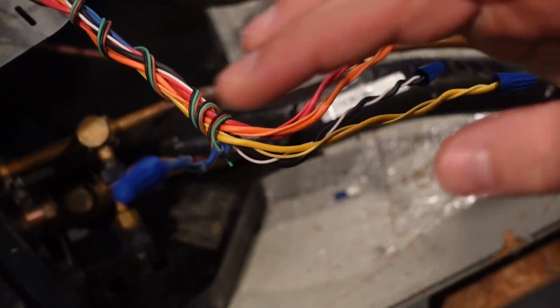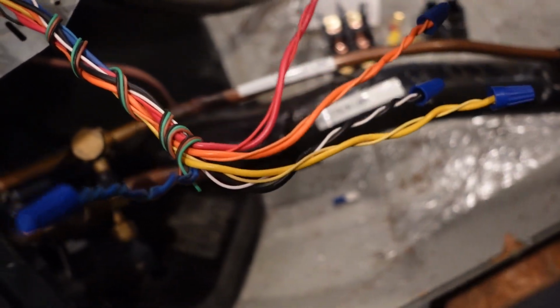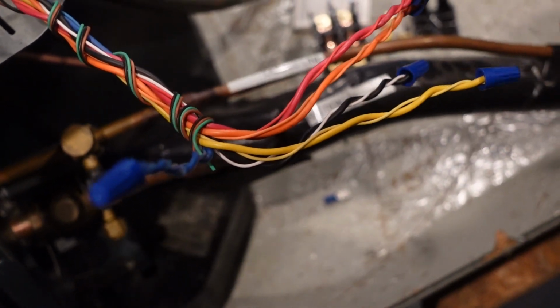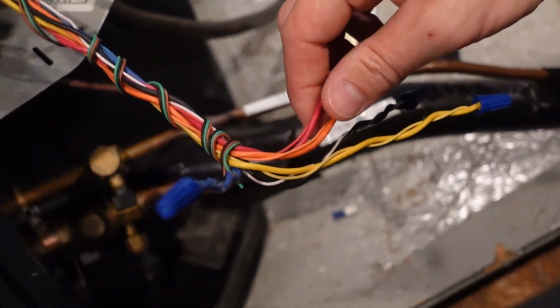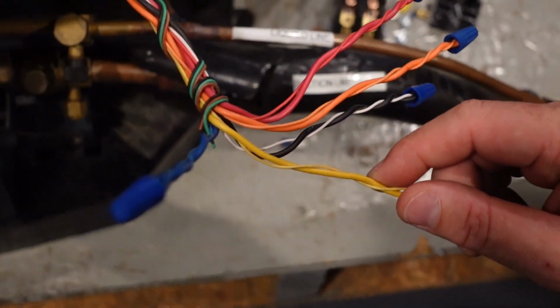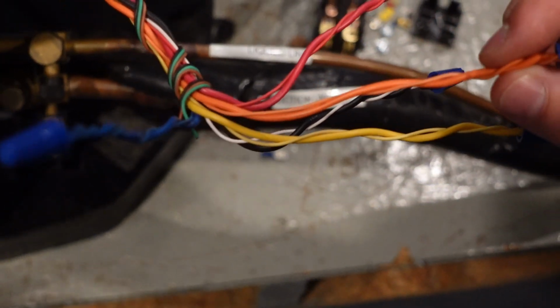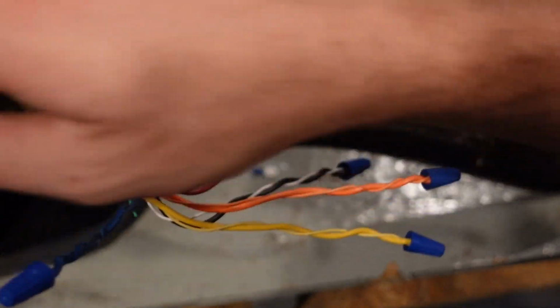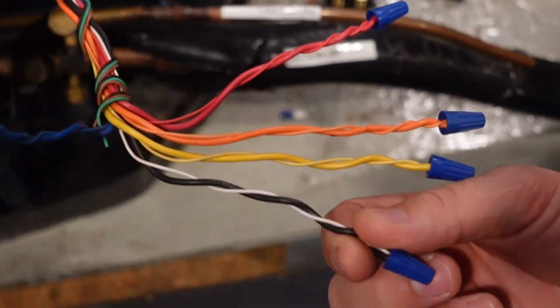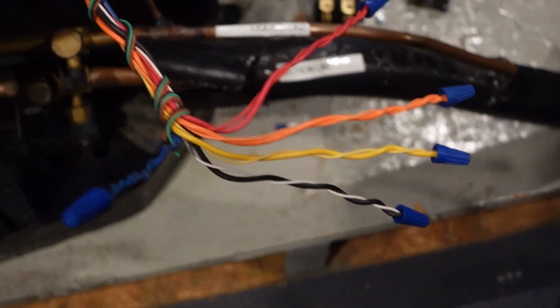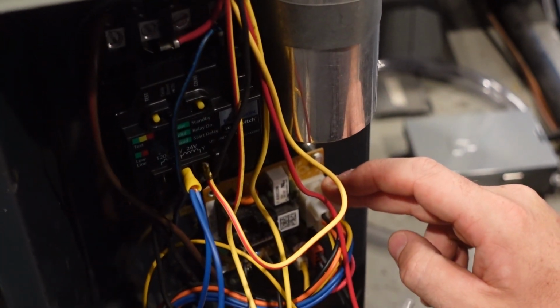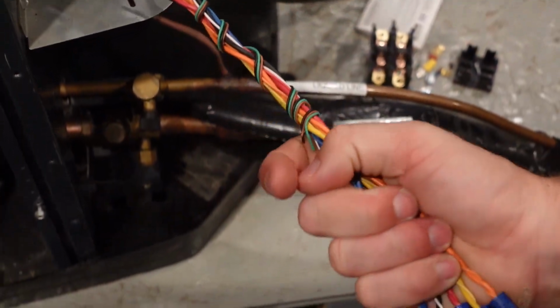to this common wire. Or if I want to see if I have a hot signal, I've got to check from here to here. I cannot check from here to here. That doesn't give me a good reading. So R, common, our Y, which is our compressor, our orange, which is our reversing valve over here, and our W, which sends a signal back from this defrost control board to the heat kit on the indoor unit. And that's all of your low voltage wiring.